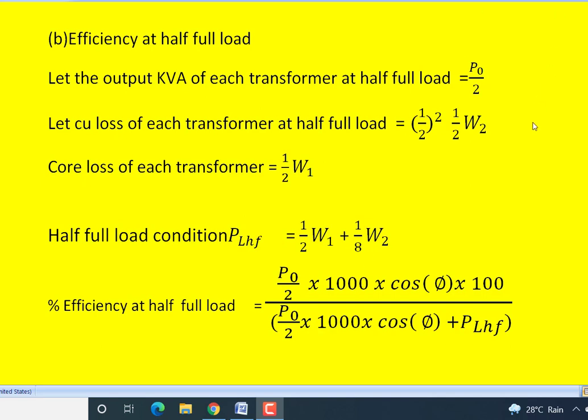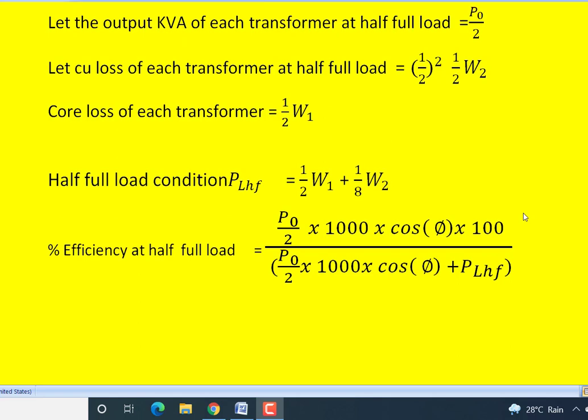The major disadvantage with this method is identifying or finding the two identical transformers, which is practically very difficult. But once we find them, it is very easy to find the temperature rise of each individual transformer, and it is also a one-time test by which we can calculate the core loss and the copper loss of each transformer.